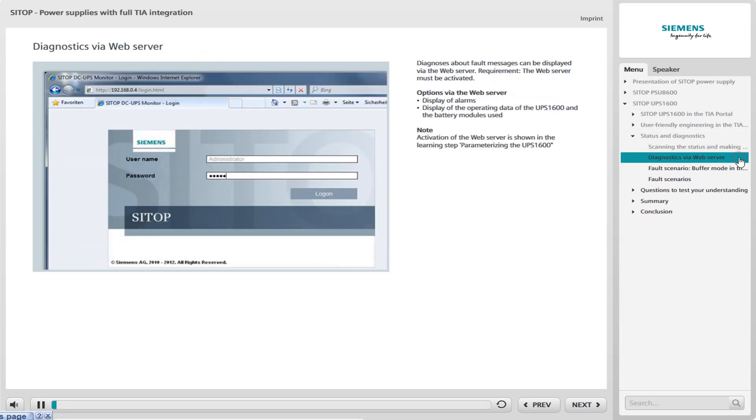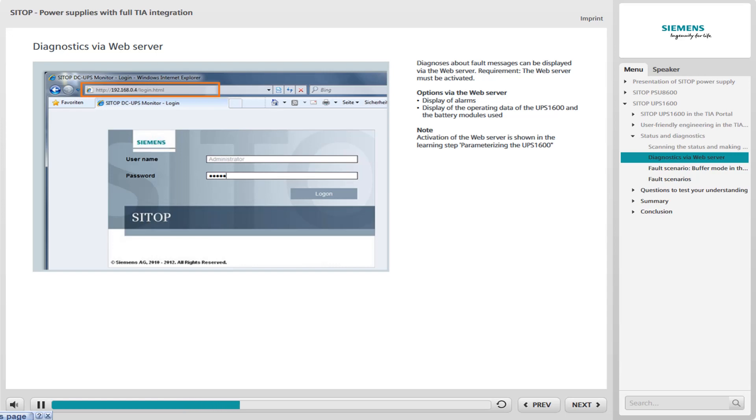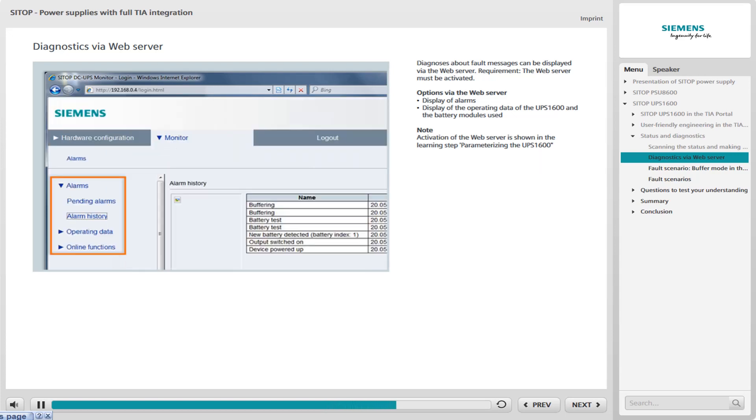You can also display diagnoses about fault messages via the web server. The web server must be activated for this purpose. After entering the IP address of the UPS 1600 in the address line of Internet Explorer, a page with login information appears. Log in here with Administrator and use the password admin. In the login window, you have the option of viewing the sent alarms or the status of the added battery modules.